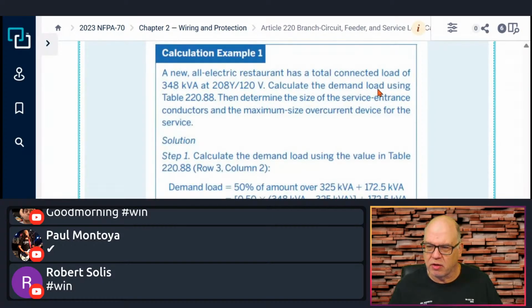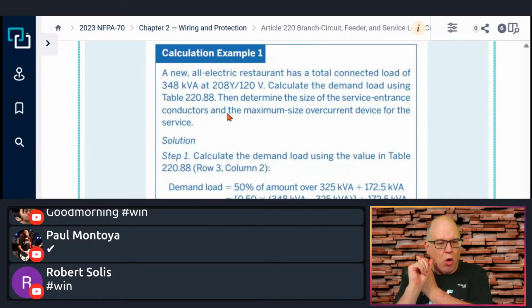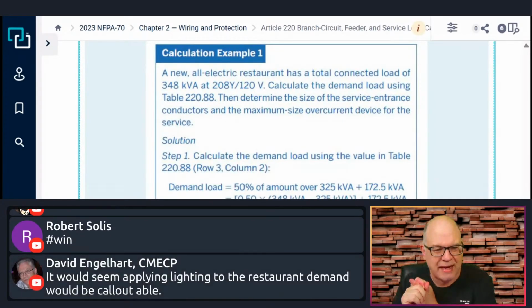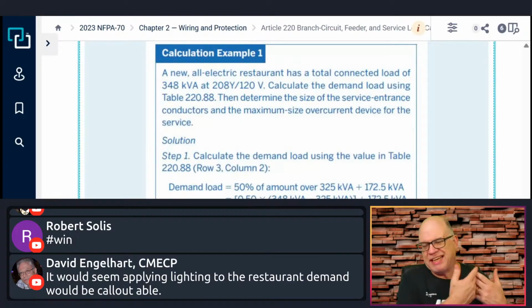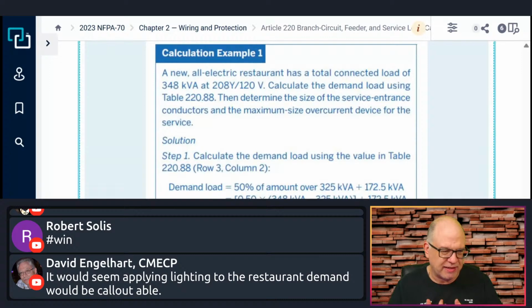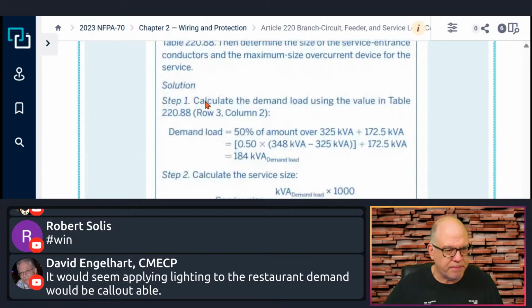Calculate the demand load using table 220.88, or what we call the demand or calculated load, essentially the same thing. They're all resulting in applying some type of demand factor that changes the connected load into what we call a calculated load.